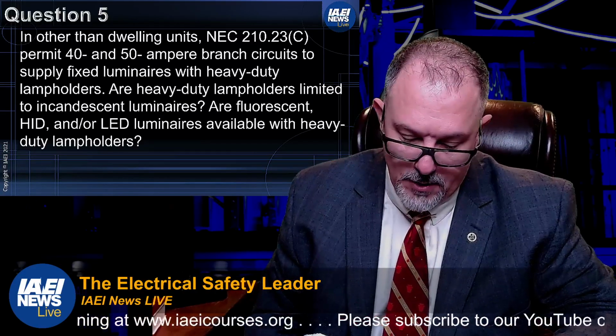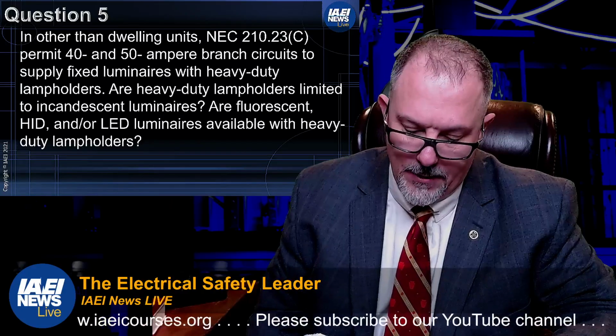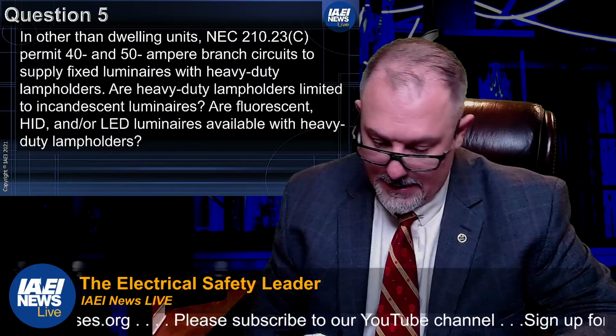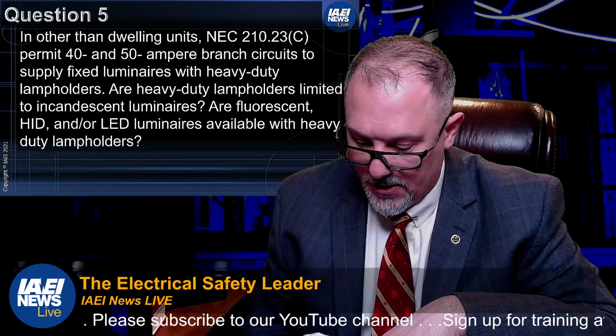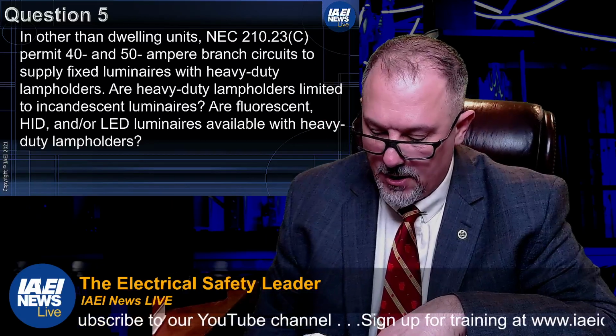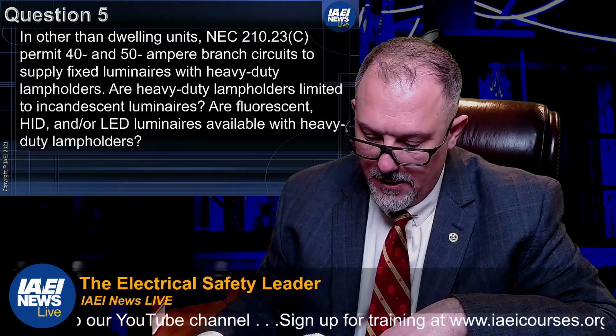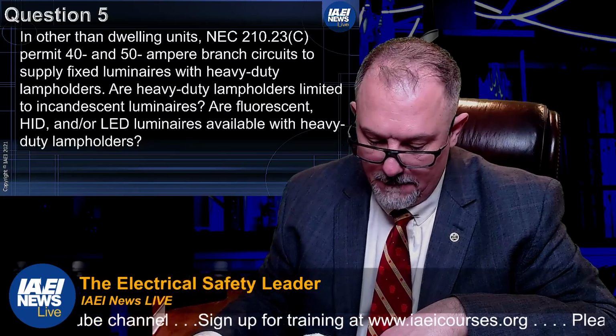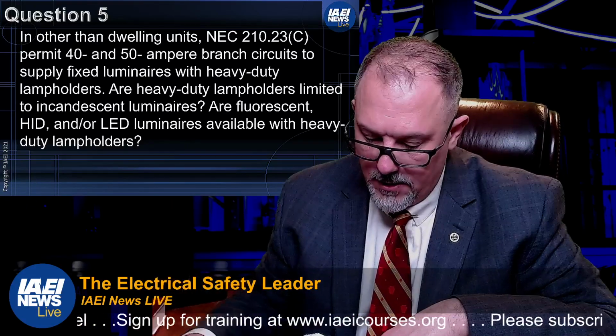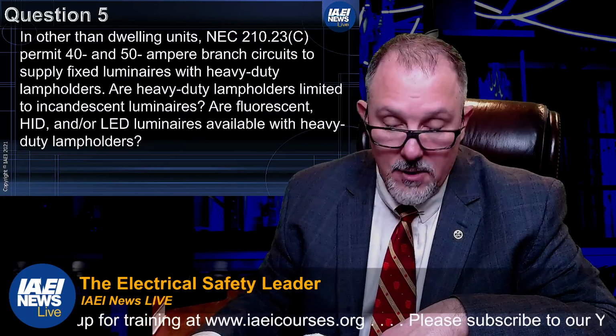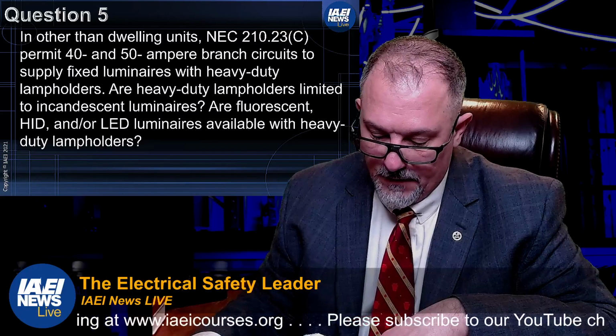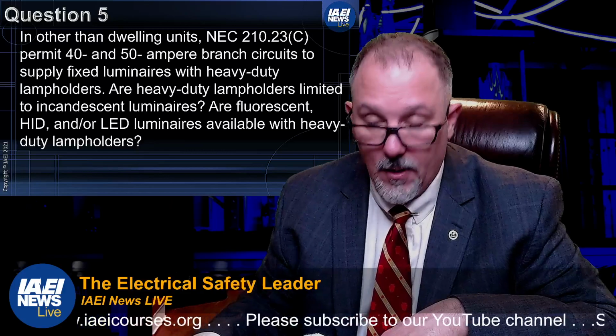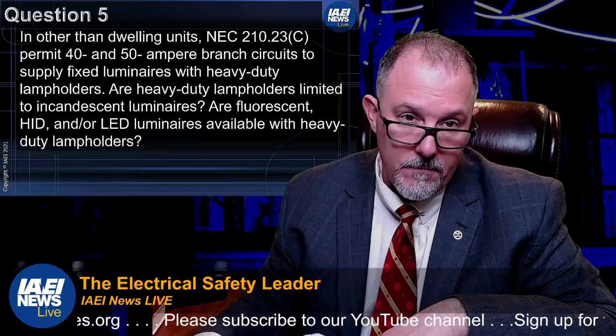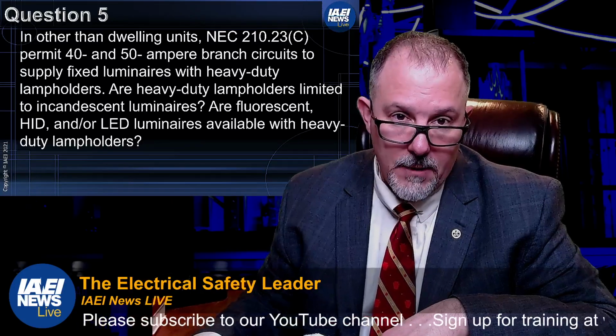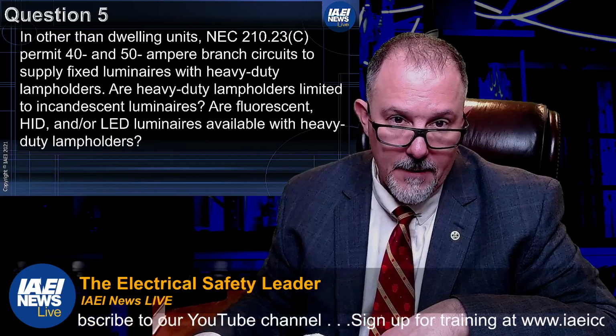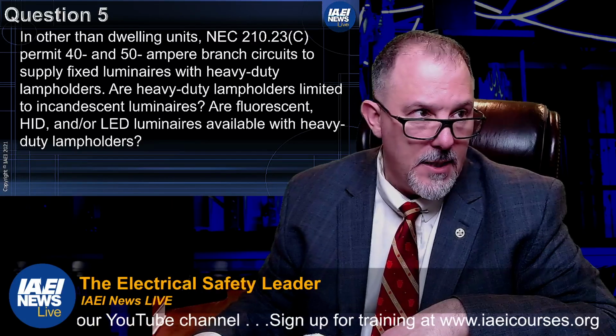210.23 is permissible loads, multiple outlet branch circuits. And C is for 40 and 50 ampere branch circuits. So a 40 or 50 ampere branch circuit shall be permitted to supply cooking appliances that are fastened in place in any occupancy. In other than dwelling units, you can supply lighting units with heavy-duty lamp holders, infrared heating units, or other utilization equipment. So I can put in heavy-duty lamp holders. Now the question is, what comes in those lamp holders?